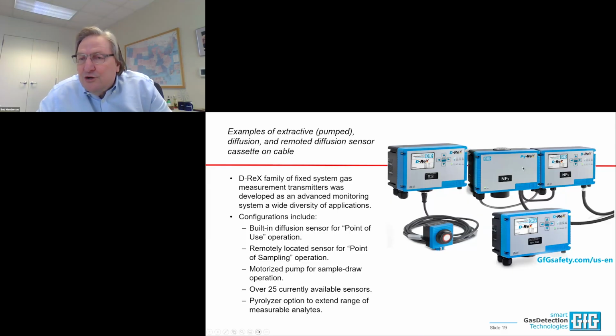Now, to be able to measure even more kinds of gases than we have sensors available for, we can sometimes process the gas that's coming in. The unit on the right is a pyrolyzer, and the way that we use the pyrolyzer, I'm sorry, the unit in the middle is the pyrolyzer. The unit on the right is the pump equipped DREX. And before the sample gets to the sensor in the unit on the far right, it goes through the pyrolyzer. And as you can see, this is designed to measure NF3, nitrogen trifluoride.